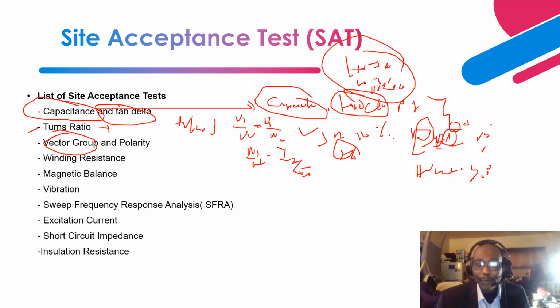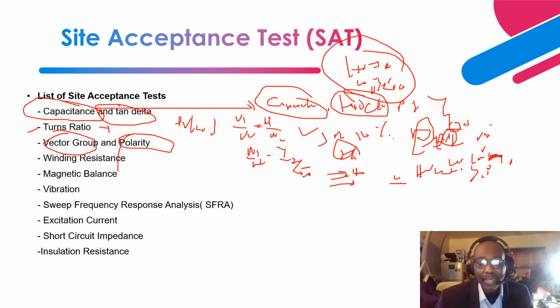On the other hand, if we have 11 here, that means that the low voltage side leads the high voltage side by 30 degrees, because 11 is 30 degrees, right? Okay. So when we do the turns ratio, that is when we check the vector group, and we also perform the polarity, right? So the polarity will be the direction and an instantaneous value of the current, right? So for the high voltage side, we have current going in, and for the low voltage side, we have current coming out. So that is what we check for.